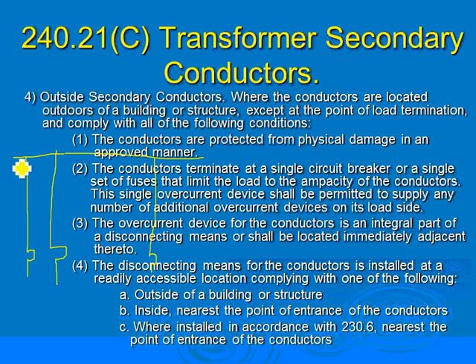The only limitation, guys, that you're going to see is the short circuit. With no limitation in distance, the circuit breaker must be able to protect the feeder as well as the taps from short circuit and ground fault. So that's the only limitation.